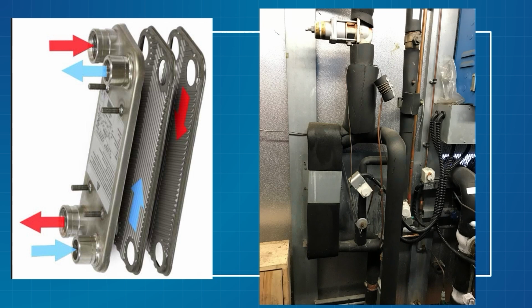What temperature is that gonna boil at? Saturation. How do we control that? EPR. So on the primary side, we're gonna see an expansion device, right? On the outlet, we're gonna see an evaporator pressure regulator, because it's an evaporator. Make sense? On the secondary side, it doesn't get any simpler than this.